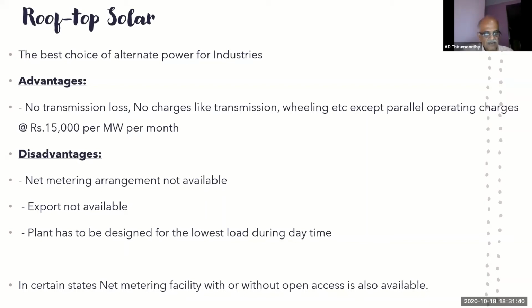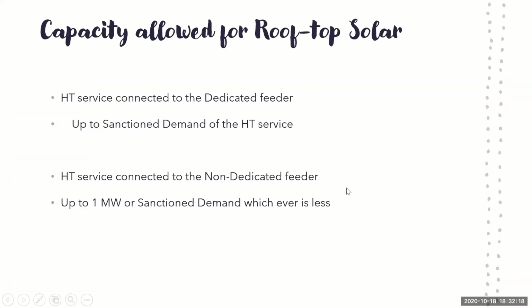But in certain states, net metering facilities are available for HT industries, and certain states even permit open access in this plant. So that means if you have excess power in this unit, you can export to the grid and you can use that power anywhere else in your other units. That facility is also available in certain states, but not in Tamil Nadu. In Tamil Nadu, there is no net metering, and ultimately there is no open access for this plant. For the plant that is put inside the premises, that is not allowed. So that is the scheme available as on today.